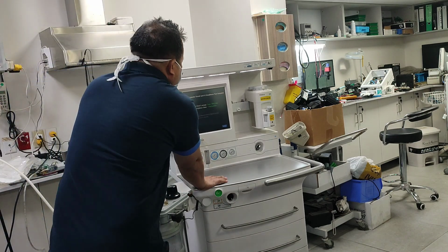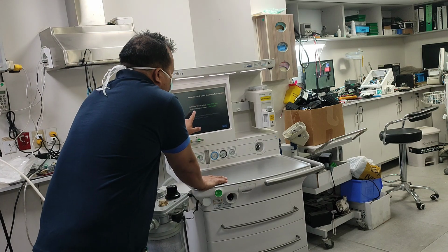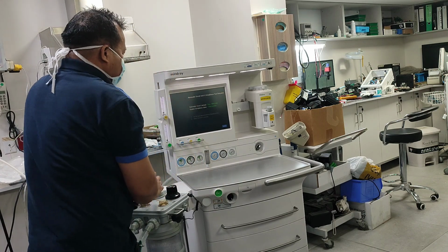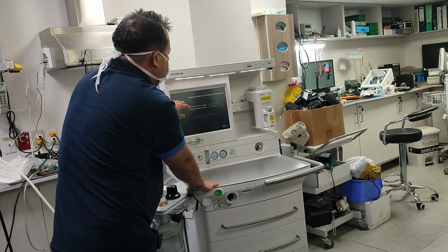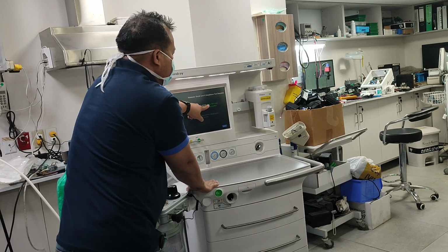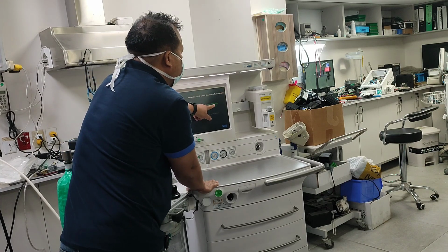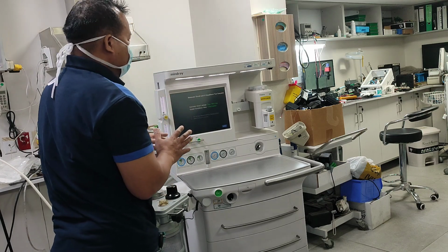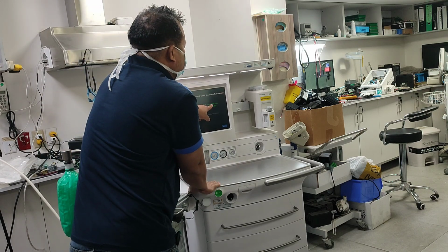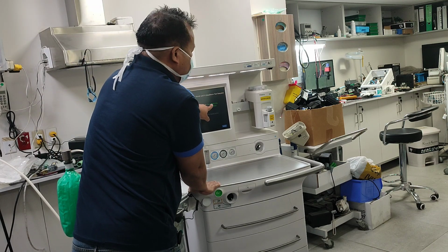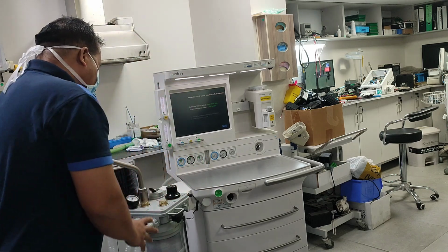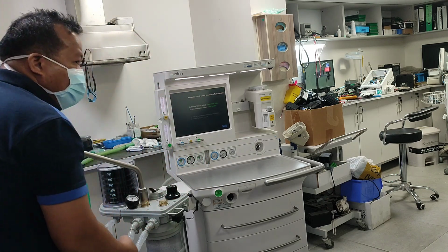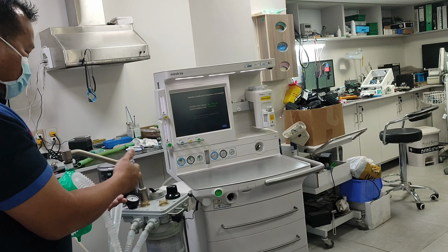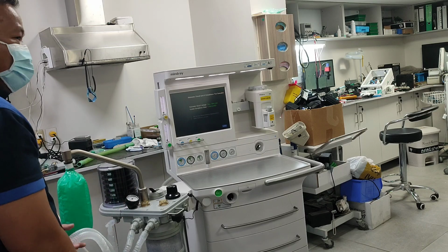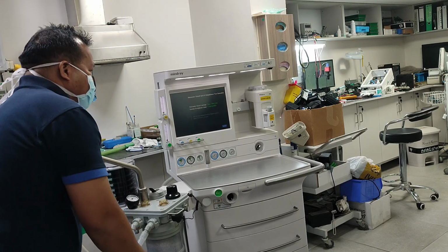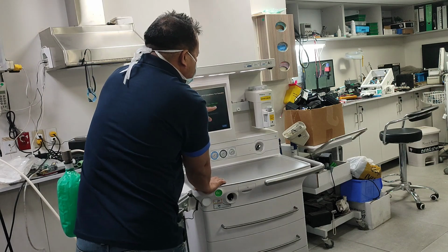So here, it has already finished the automatic leak test. The machine will tell you that the automatic leak test passed. There is a gap of 70 milliliters per minute, the leakage only. But this is acceptable until 300 ml. So this one is 70. There is a leak, but we don't know where the leak is. Maybe in the tubing. In the tubing there is a dead space, so maybe the 70 ml is from there also.